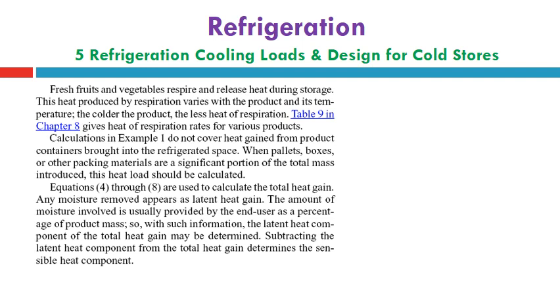So for various products we can get all the information on respiration rate to estimate the respiration load of these products according to the delta T and its rate of respiration, based on the values of various products listed in table 9 in chapter 8. Calculations in example 1 don't cover heat gained from the product containers brought into the refrigerated space when pallets, boxes or other packing materials are a significant portion of the total mass introduced. The heat load should be calculated.